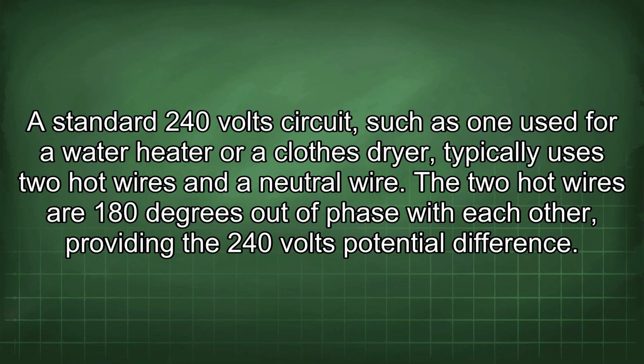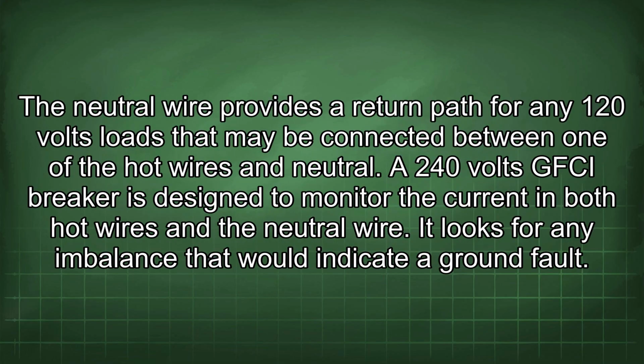A standard 240-volt circuit, such as one used for a water heater or a clothes dryer, typically uses two hot wires and a neutral wire. The two hot wires are 180 degrees out of phase with each other, providing the 240 volts potential difference. The neutral wire provides a return path for any 120 volt loads that may be connected between one of the hot wires and neutral. A 240 volts GFCI breaker is designed to monitor the current in both hot wires and the neutral wire. It looks for any imbalance that would indicate a ground fault.